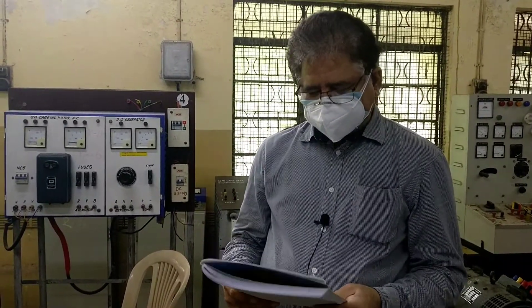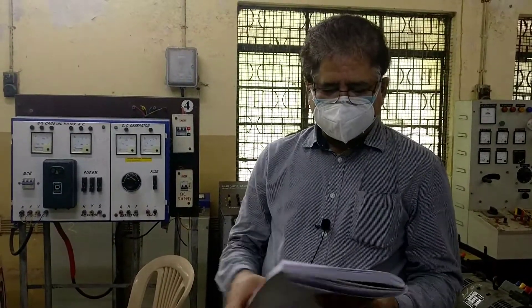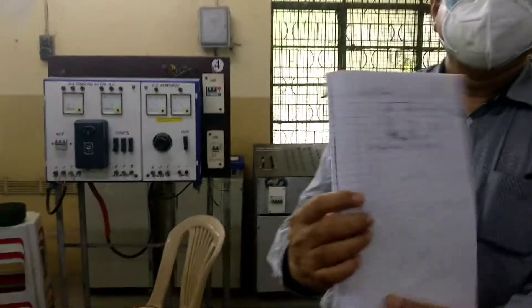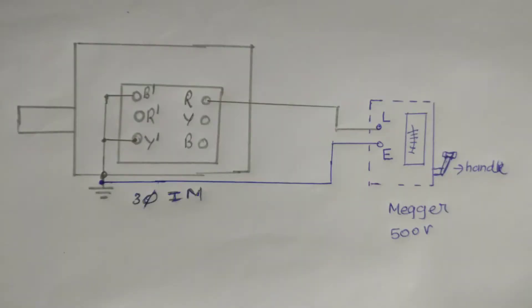Now for the procedure part, we refer to the connection diagram. As our motor carries six terminals, it means each winding is separate — that is the R phase winding, the yellow phase winding, and the blue phase winding. As per the procedure, when we measure the insulation resistance of one winding, the other two windings have to be shorted and connected to the earth.